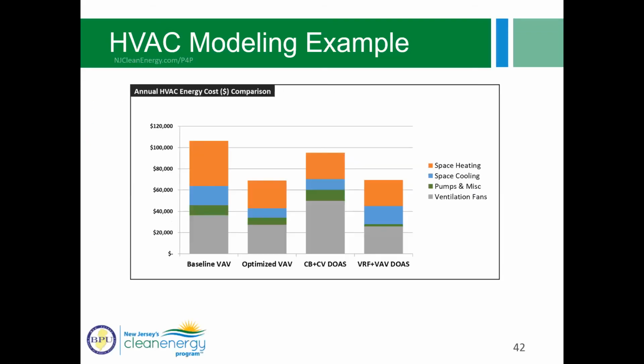So this is always fun, right? So interesting to look at how these different options compare. On this graph, you'll see on the y-axis the annual energy cost. On the x-axis, you'll see the different systems I just talked about: the baseline VAV, the optimized VAV, chilled beam with the constant volume DOAS, and then VRF and the variable air volume DOAS. So some takeaways here. The optimized VAV and the VRF with the VAV DOAS were the top performers in that they had the lowest annual energy cost.